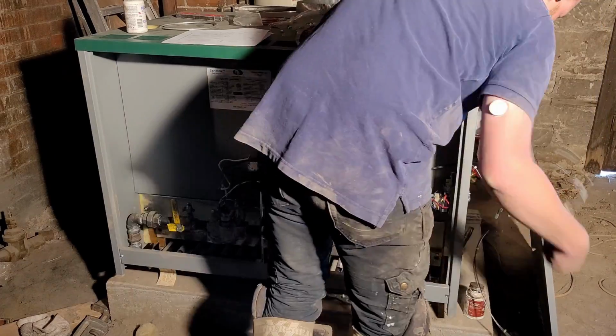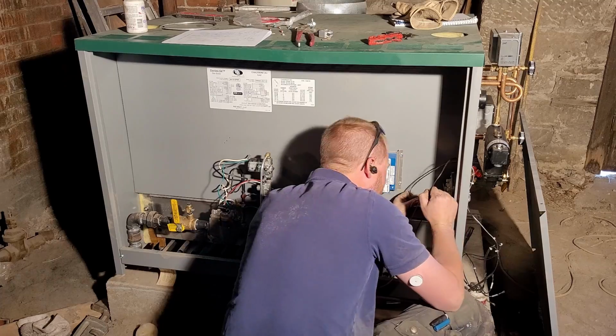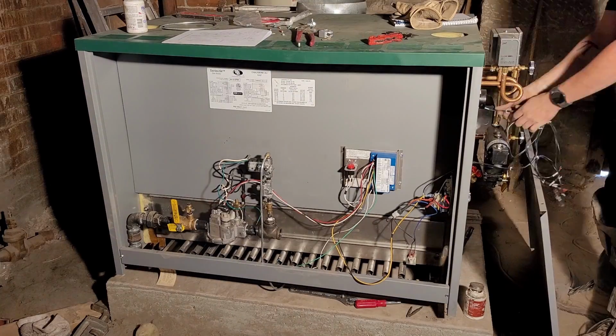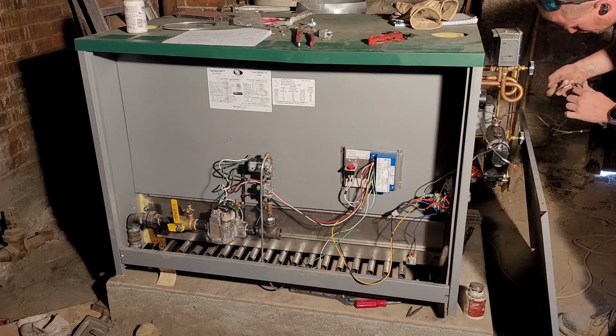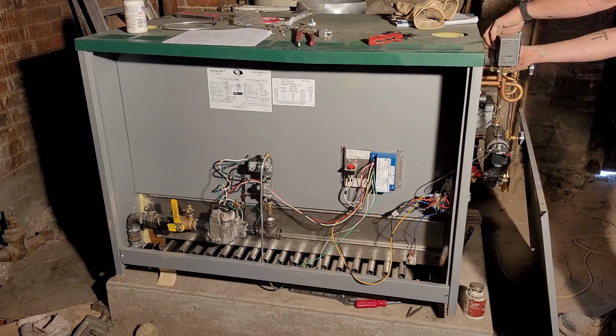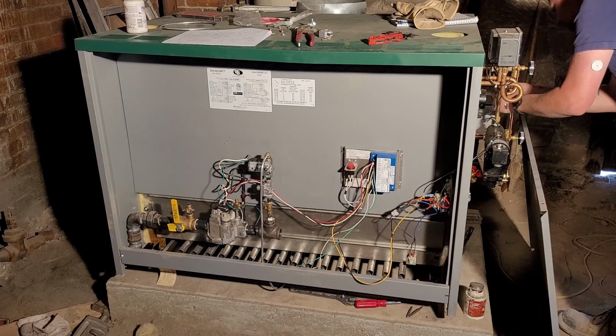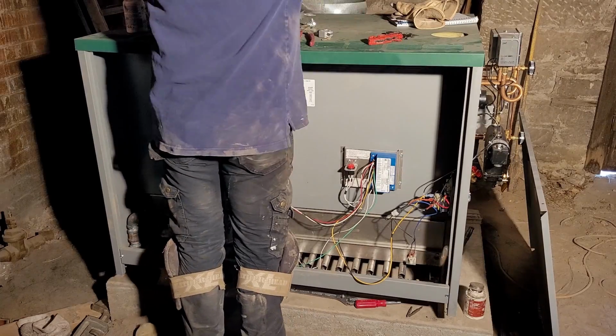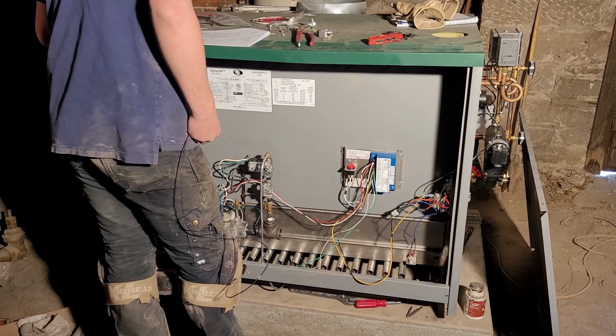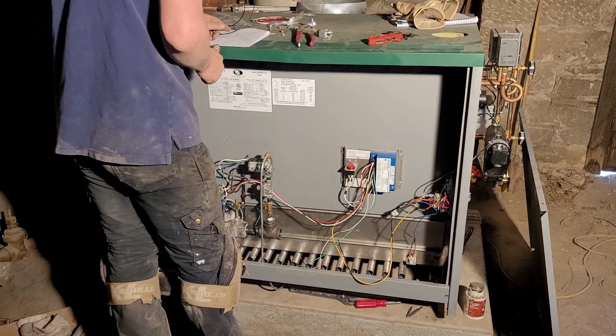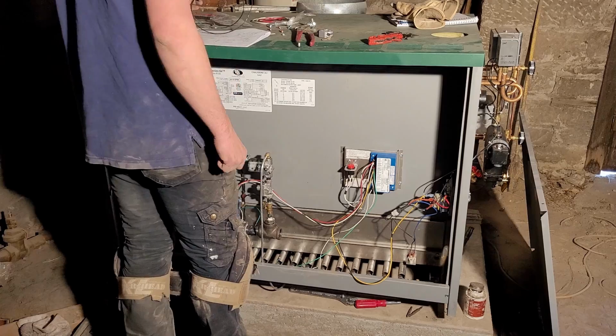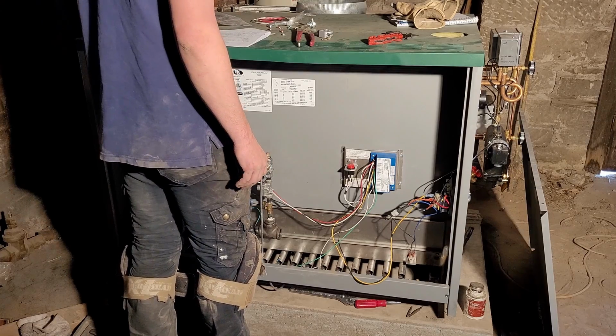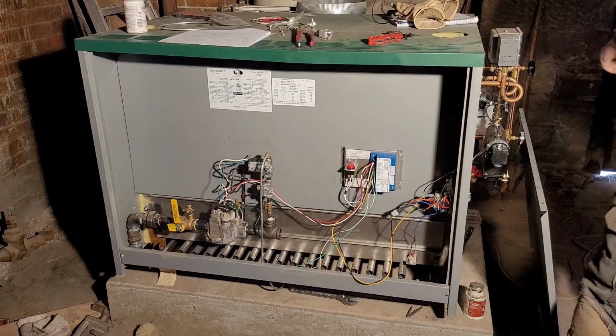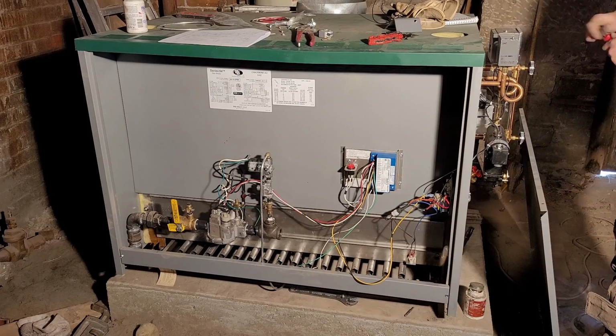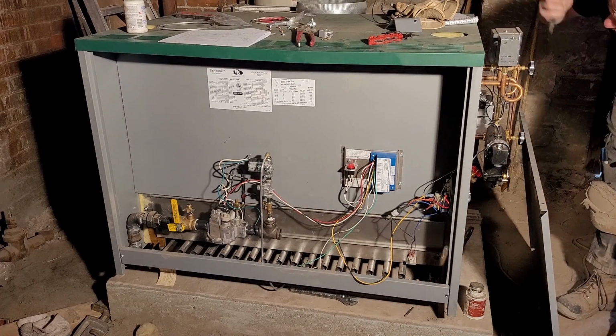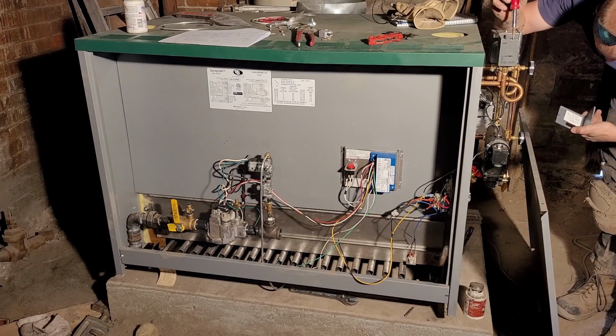Now you'll see me installing the wiring harness that goes through all the pressure trolls and the low water cutoffs and the draft switch and all that. Again, it's just a big long series circuit. All of these switches have to be working. Everything has to be closed for it to fire the boiler. If any one thing goes wrong, none of this will work. And really, one of the big advantages of the more modern electronic controls is that it's pretty tough to actually make a boiler fire. A lot of things have to be right for it to fire.